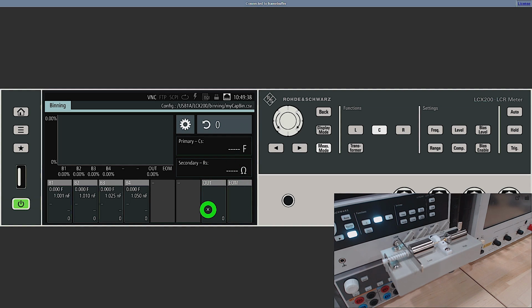Now, once you put it into this mode, you essentially have this triggered menu. You can either trigger externally with software or with some signal from the outside, and you can route the measurements also through the digital I/O in the back of the unit so that you can have some automated measurement. So there's a capacitor in there already, so let's go and press the trigger button. And there you go, it's going to make our first measurement. And you can see that first capacitor falls in the bin of below 2.5%, which is good.